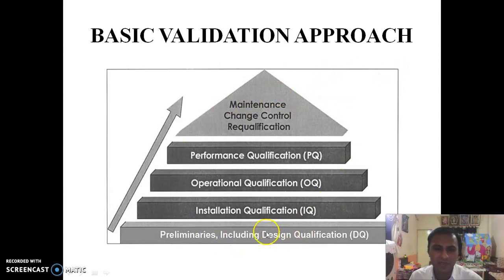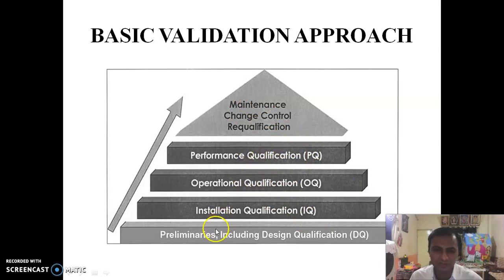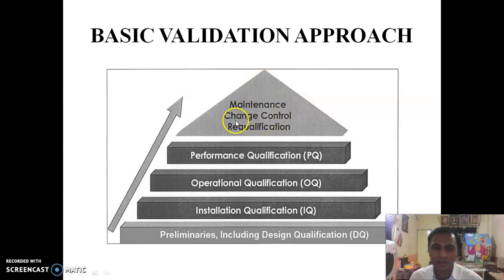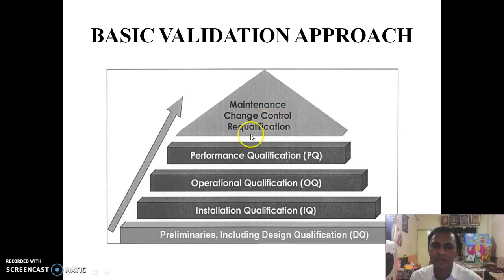In the qualification pyramid, you can see the types of qualifications performed to qualify a particular instrument. First are preliminaries including equipment design qualification, then installation qualification, operational qualification, performance qualification, and lastly ongoing maintenance. If any change is required to the procedure, process, or equipment, re-qualification is needed.